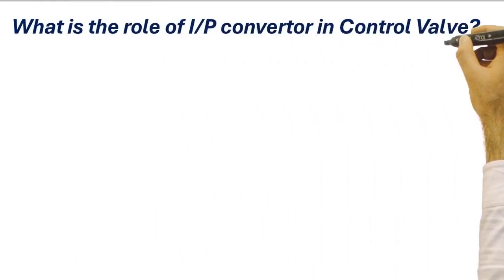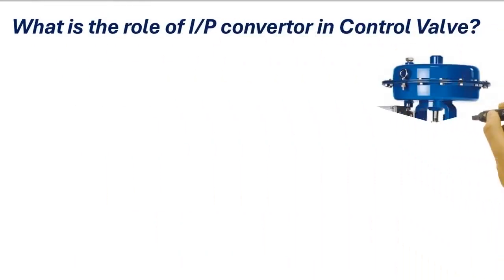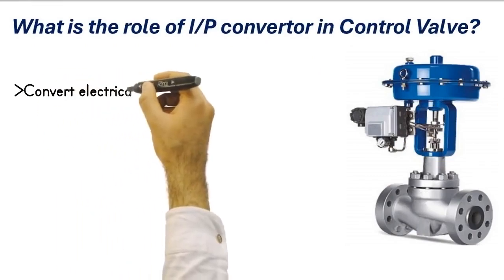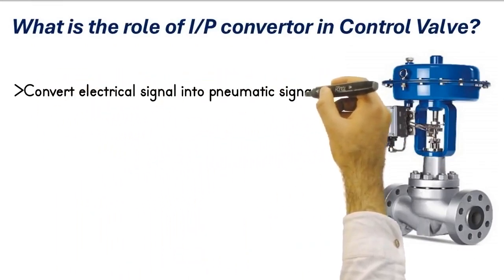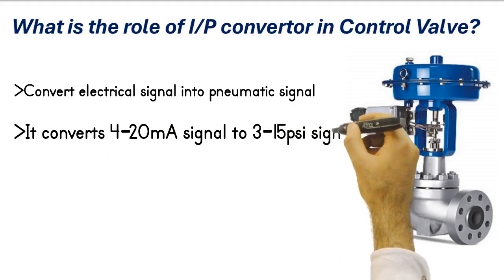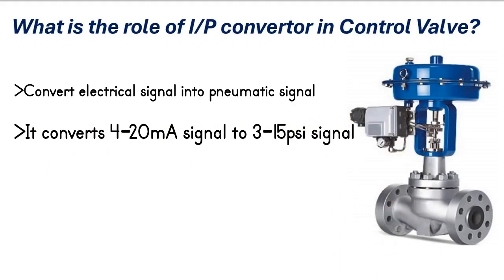What is the role of an I/P converter in the control valve? An I/P converter plays a crucial role in a control valve. It converts an electrical current signal into a pneumatic pressure output. Specifically, it converts a 4 to 20 milliamperes current signal to a linear 3 to 15 PSI pneumatic signal.